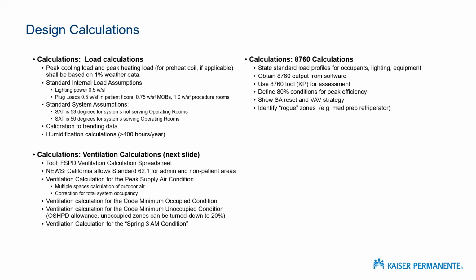For humidifiers, we really want to avoid them as much as possible. In California, OSHPD allows us not to install humidifiers if we don't have the design conditions to need them, or if we can show by calculations that they are not needed. Our rule of thumb is that if humidification is needed less than 400 hours per year, then installing a humidifier does more harm than good. So if you put in humidifiers, we're always going to ask the question to see those annual calculations and the psychrometrics around them. I'm going to talk about ventilation calculations on the next slide.